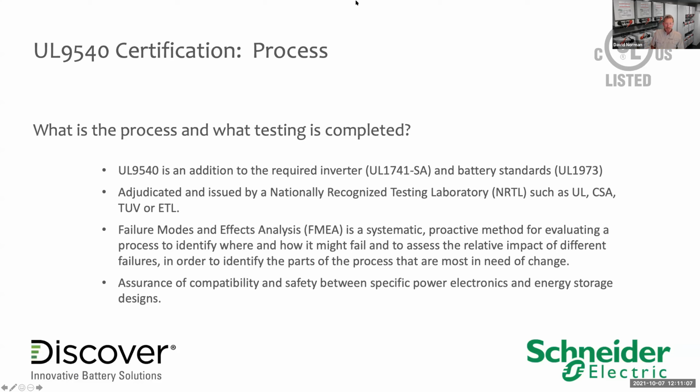What they then ask for is system level safety checks, where they do some testing based on the collaborative energy output and controls and safety mechanisms of both the inverter charger system, any of the disconnects, overcurrent disconnects and otherwise, and the battery itself, the BMS's internal intrinsic safety protections.